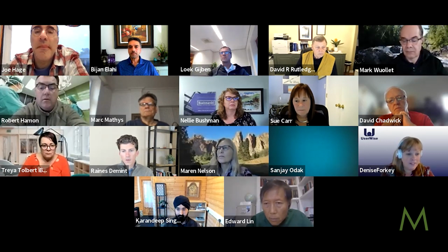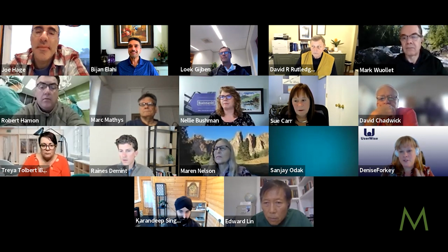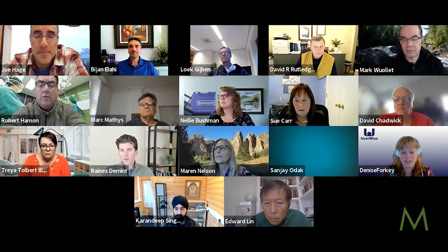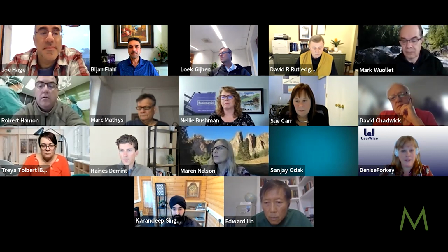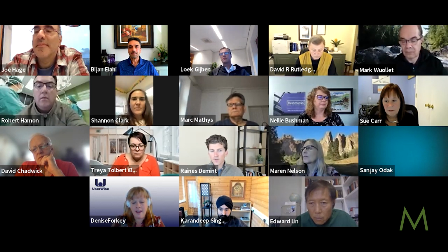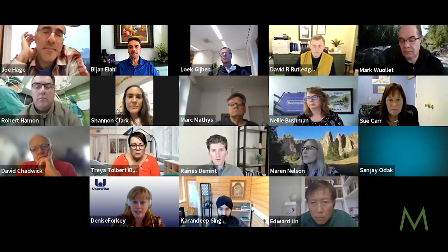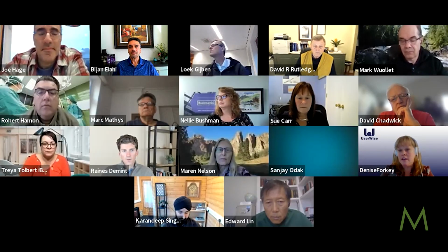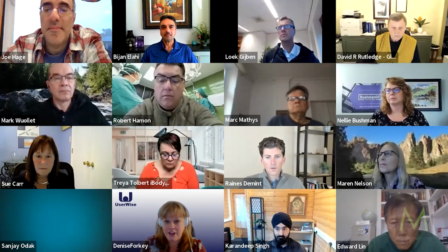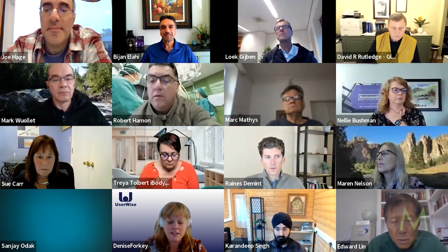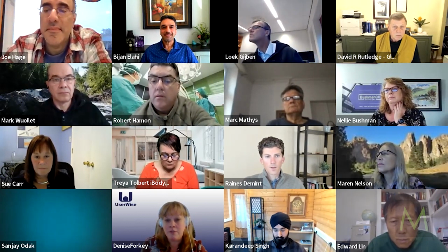I can think of a few people who would love to watch it if you ever do that. Denise? Yeah. Hi, thanks so much for your talk, Bijan. Really enjoyed it. I'm with UserWise. We focus on usability consulting, and I just had a quick question. Thank you for recognizing that 62366 makes a comment that it's not easy to estimate occurrence, as does FDA. But yet we still are seeing a lot of companies focusing a lot of effort on estimating both a pre-mitigation occurrence and a post-mitigation occurrence. And that can be quite challenging because it takes up a lot of time and effort. And there's lots of discussions when maybe a pre-occurrence is even less valuable than a post-occurrence. Do you have any thoughts on whether a pre-occurrence is really necessary, because I know the 14971 says that you need to evaluate risk pre-mitigation.